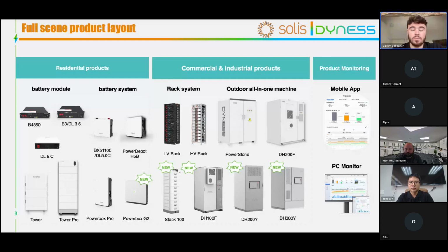So what do we do? Just a quick overview. I will be diving deeper into the residential products, the specific individual ones. On the top left, we've got our rack systems, the B4850 and the B3. The B4850 is a 2.4 kilowatt hour module that can be installed up to 40 times in parallel, which is very good for flexible systems. Same as the B3. We have recently brought out a B4850 box, which allows you to put 2 of these in. I will be talking about that a little later on.